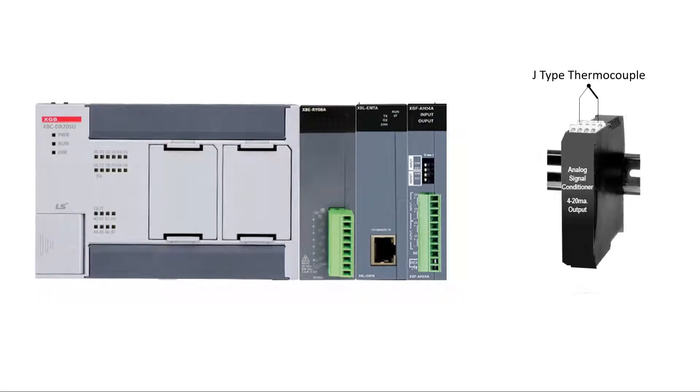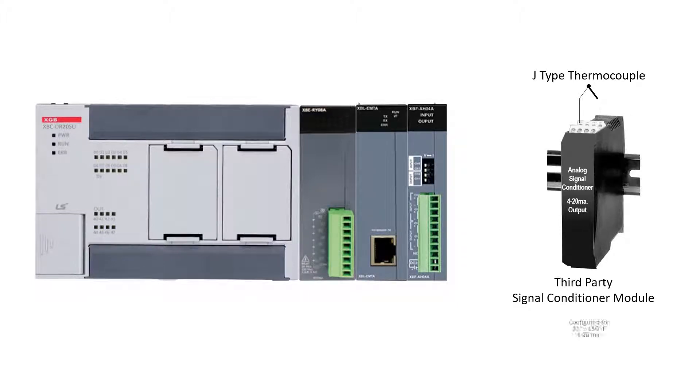The J-type thermocouple is connected to a third party signal conditioner. The signal conditioner is configured for a full scale span of 32 to 150 degrees Fahrenheit. A 4 to 20 milliamp analog signal is sent to channel 0 of the PLC analog input module.